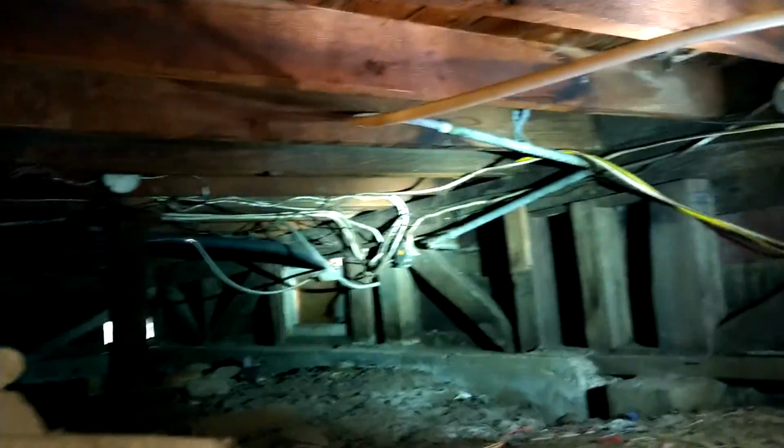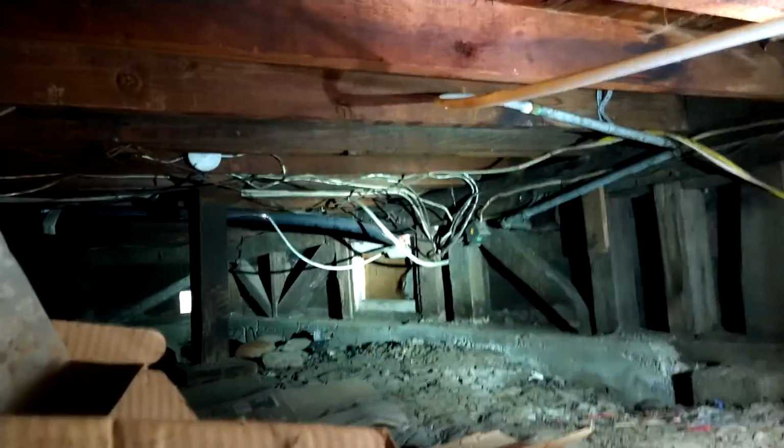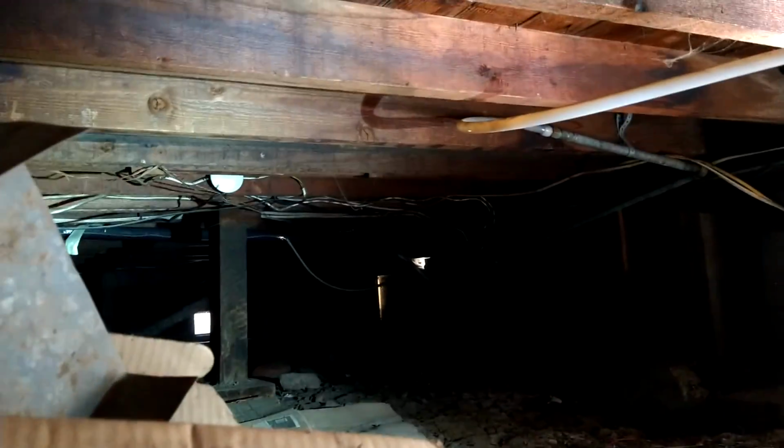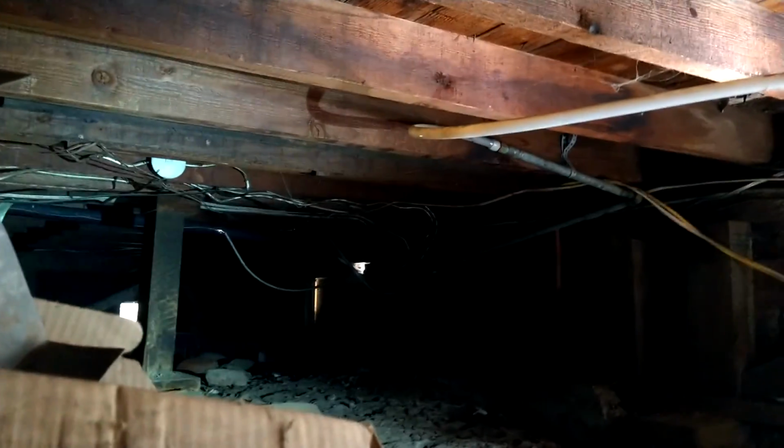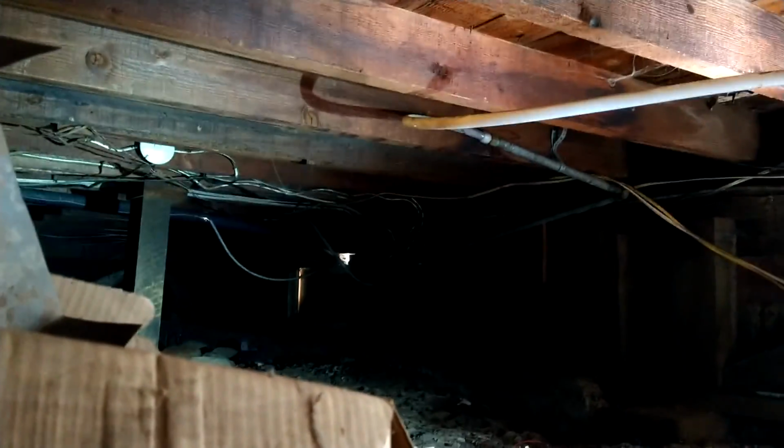And there's still, as you can see, rat droppings, so there's still rat activity. And under here, same issue with the abandoned wire and wires that should be properly strapped up. Could you shine your flashlight so I can video it? Thanks. And all of this, under these rooms that have the knob and tube, there's an electrical hum, like constant. So you can tell that it's not grounded because of the sound.